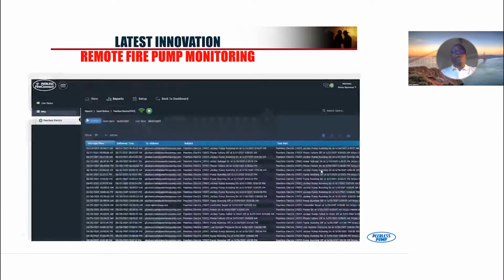And it's available every time you have an incident. It is live information to all the users that you want in the system. You send them a text message, you send them an email, in real time to let them know that, hey, your jockey pump has started. If your jockey pump didn't stop in 2 or 3 minutes, why? Okay. And you can go back on your live app and see that the jockey pump continues to run. Or if it continues to run and then the main fire pump starts, you're going to get another notification that your main fire pump has started. So at least you know immediately what's going on in your fire system, and it will help you manage and coordinate with the fire authority exactly what's going on.